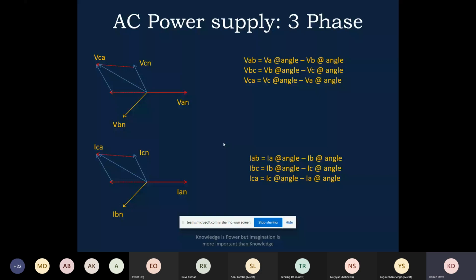See, this is an important parameter when we look at generator faults, generator protection, relay behavior, specifically line protection relays and line faults that we analyze. At that time, these terms and parameters are more important to understand. Whether VAB is properly calculated or not, whether IAB is properly calculated or not, what ZAB we are getting, whether it is right or wrong, how ZAB is calculated. That is how we need to understand some basics of power system faults with these basic parameters. VAB is equal to VA minus VB. Similarly, IAB is equal to IA minus IB.